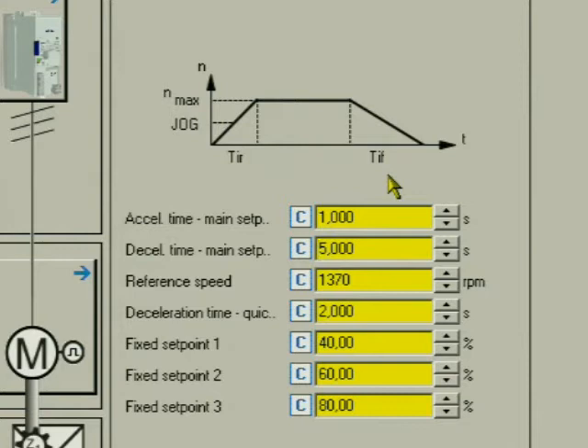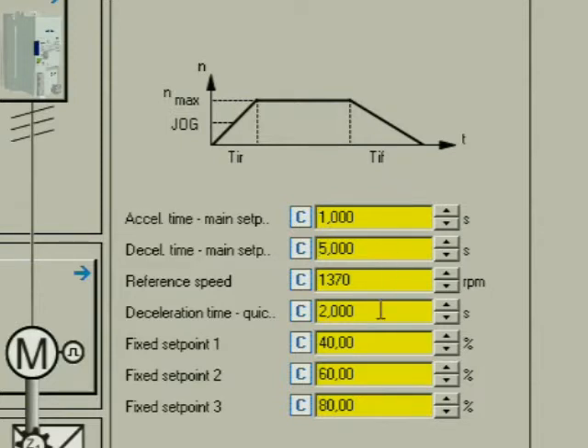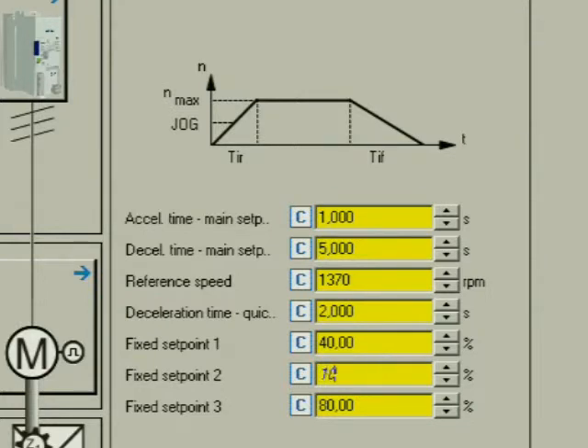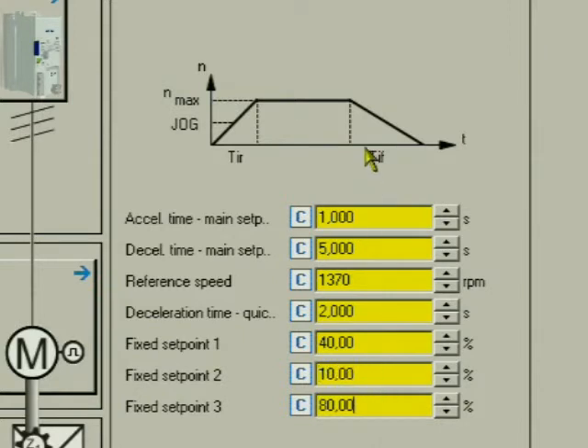For the fixed set points, the reference speed is decisive. Here we set normal speed and creep speed. Creep speed is set in fixed set point 2. We select 10 percent. Normal speed is set in fixed set point 3. We select 60 percent.